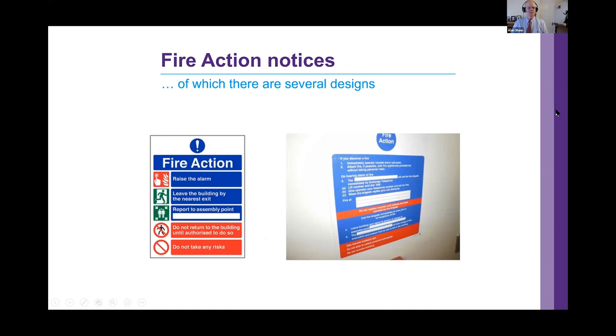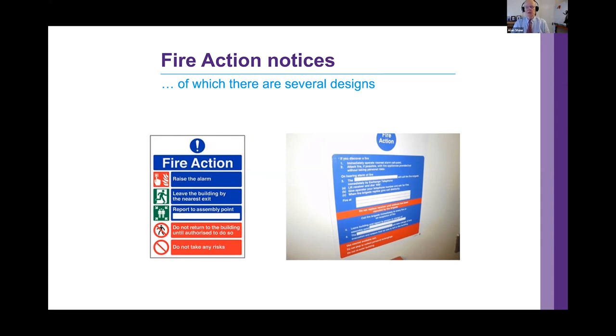Fire action notices. Blank fire action notices — how often is this seen? Too often in my experience. 'Report to the assembly point.' Where? 'What to do when you think there's a fire?' What? Useless. You must do as it says on the notice. And if not, then behaviour falls into the field of complacency. And the ultimate complacency is not filling it in — or filling it in without a permanent pen, which means the detail gets rubbed off, either deliberately or accidentally.